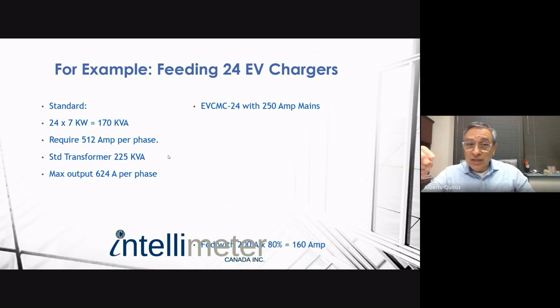When you use the EVCMC 24, you have the ability to connect 24 chargers, but instead of putting in an 800 amp breaker, you can put a 200 amp breaker. Even with the reduction required by code to 80% capacity, you can charge the cars over 12 hours, 31% of the time—that's equal to almost 4 hours of charge.